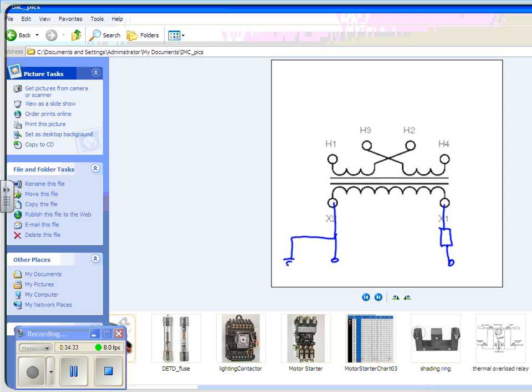So remember, we're going to fuse one side because this is being fed by what? The top side of our motor starter. There's no fuse there, right? Except the motor branch circuit. And that motor circuit might be fused at 100 amps, 150 amps, 200 amps, 400 amps, 800 amps. Essentially it's unfused. So we can protect this transformer by putting a fuse on the output.